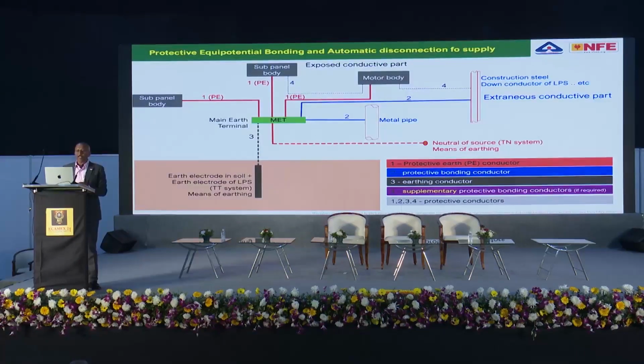The fundamental, for example, is fault protection by protective equipotential bonding and automatic disconnection of supply. Fault protection means protection against shock. Protective equipotential bonding means, and you know this very well, that in every building all simultaneously accessible metallic parts should be interconnected in such a way that there is no shock voltage. That is the first safety measure.